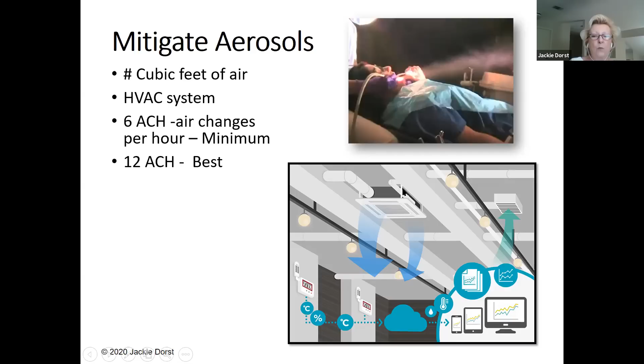And what that means is that every hour, all of the air is removed from that room 12 times. So it reduces the amount of time that is required for us not to occupy that room if we had highly infectious aerosols in that room. So I think you get the perspective of, if we can increase the number of air changes per hour, then it's going to remove any aerosols that we've generated. And as you can see on the diagram that I put on the screen, we need to look at where is the air intake with our heating and air conditioning systems, and then where does the process go through as it's filtered, and then where does it return?